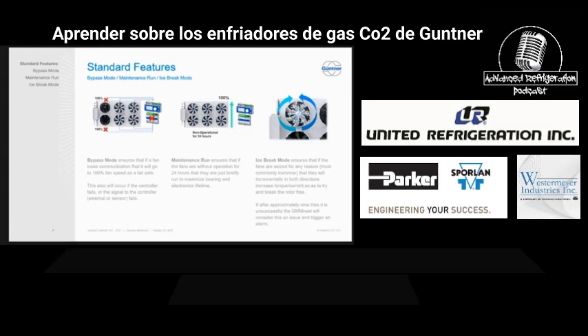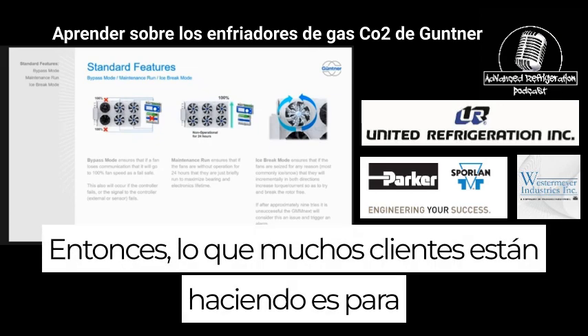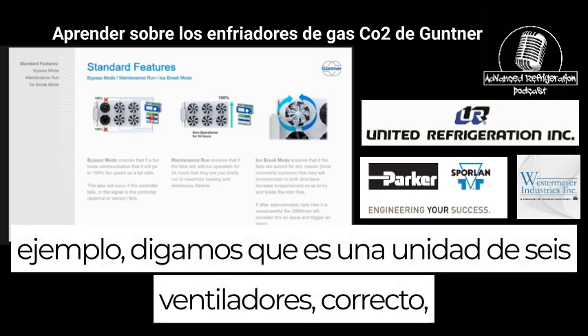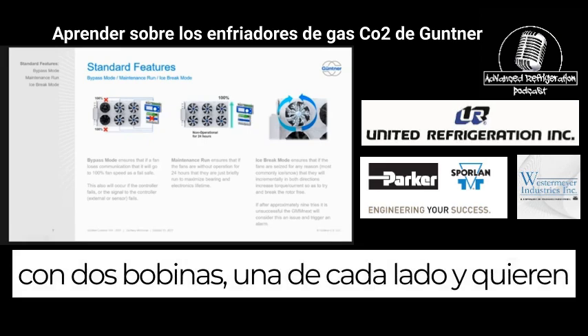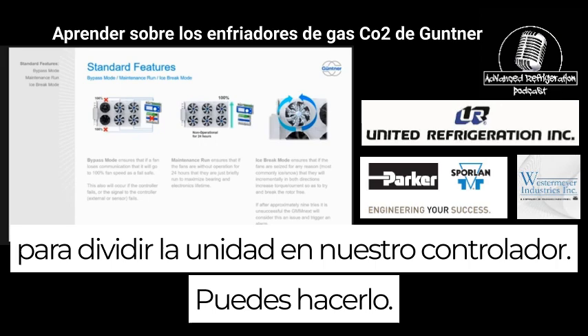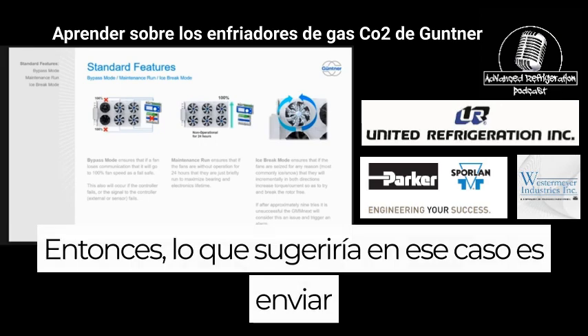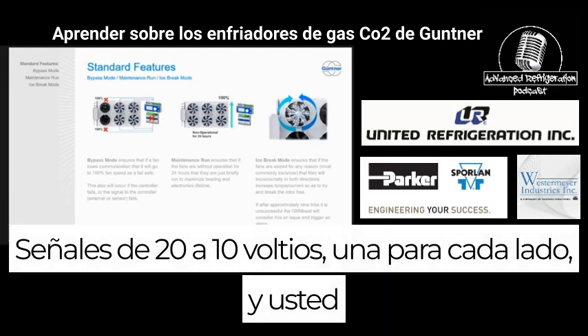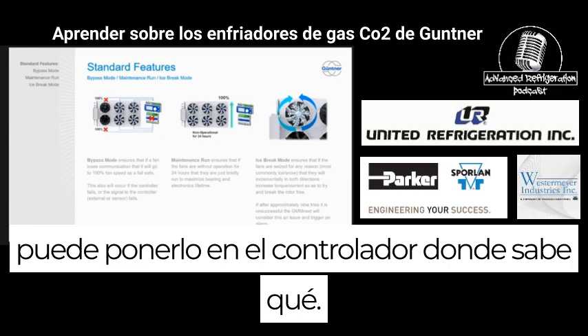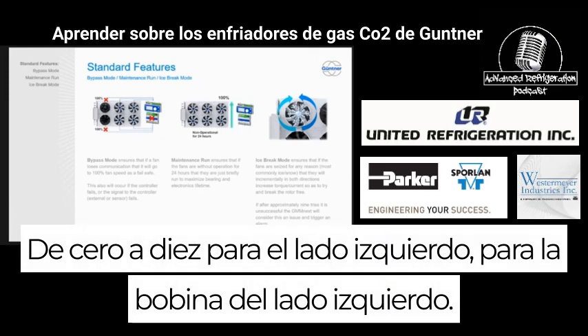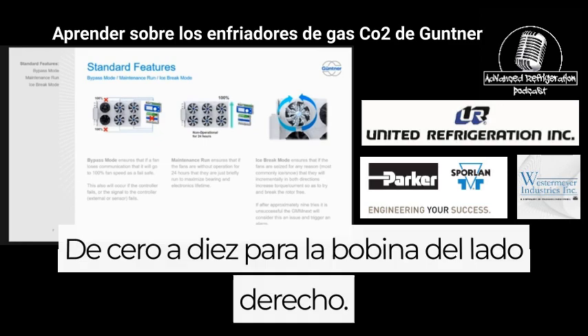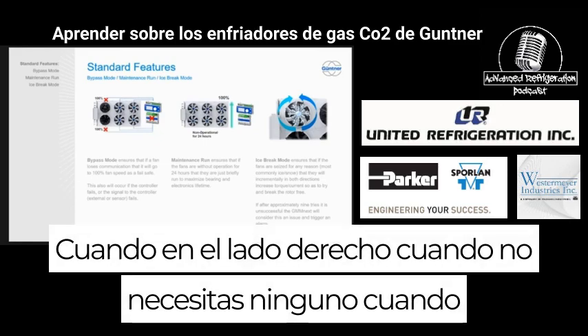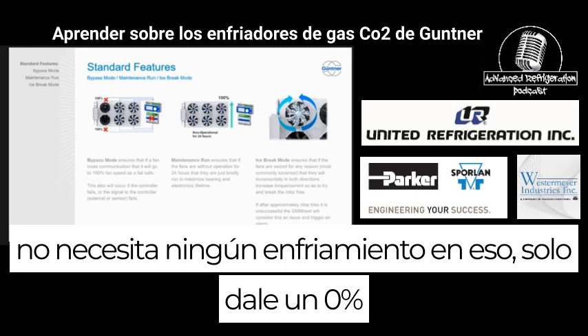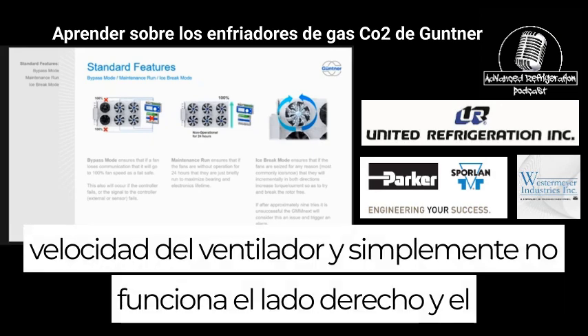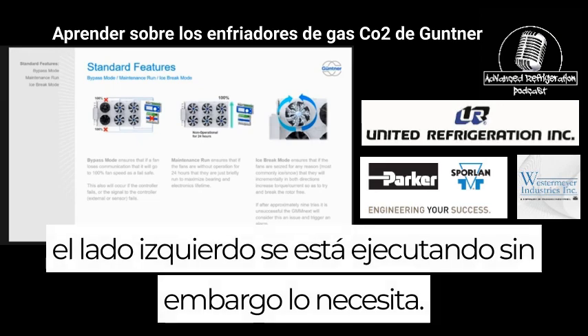Yeah, it's a good question. So what a lot of customers are doing is, for instance, let's say that it's a 6-fan unit with 2 coils, one on each side, and they want to split the unit on our controller. You can do it. What I would suggest in that case is to send 2 0-to-10-volt signals, one for each side. You can set it on the controller so that 0-to-10 is for the left side coil, and 0-to-10 for the right side coil. When you don't need any cooling on the right side, you just give it a 0% fan speed and it just doesn't run the right side. And the left side is running however you need it to.